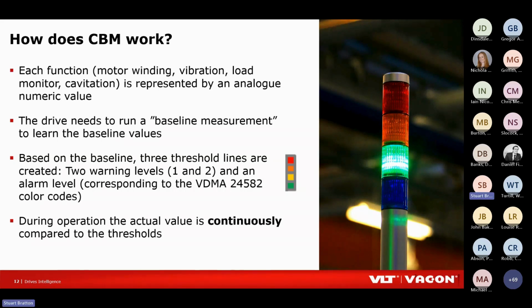So really, how deep do you want to dive into the system? If you want to manually adjust the threshold levels, you can. If you just want the drive to set the defaults, it can equally do that as well. And these baselines can either be done on the spot. So you tell the drive, I want you to start and run from this speed to this speed and baseline the measurements on the spot. Or if you want to leave the process running over a longer period of time to generate, let's call it, a better average recording of all the data, then you could leave it running as long as 6 months, gathering data before it finally generates the baseline.